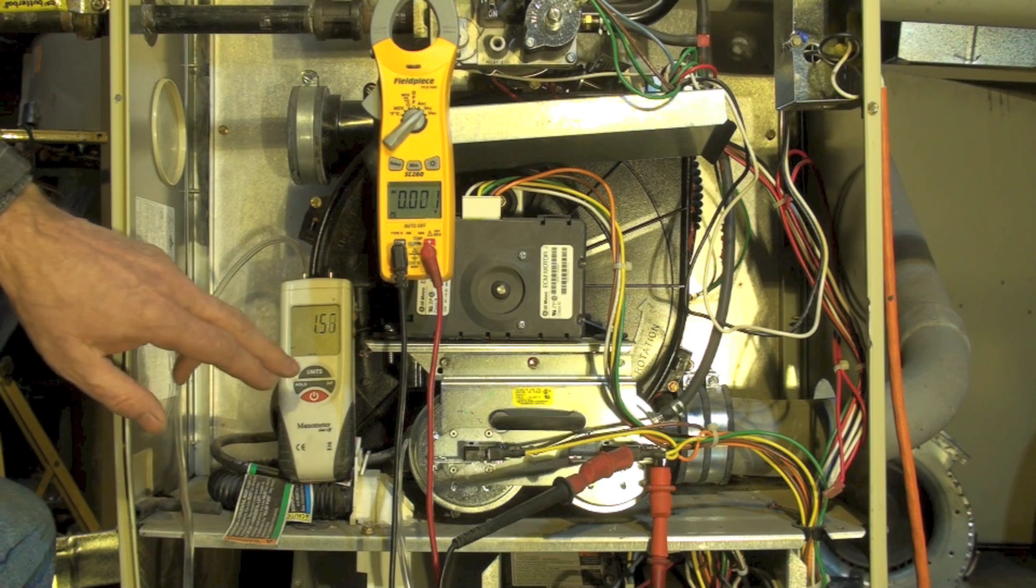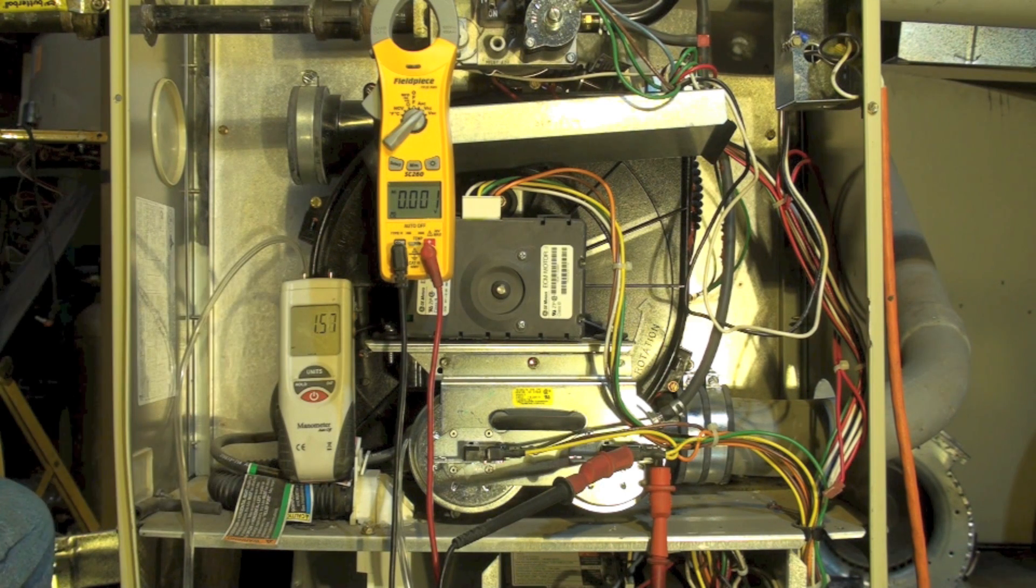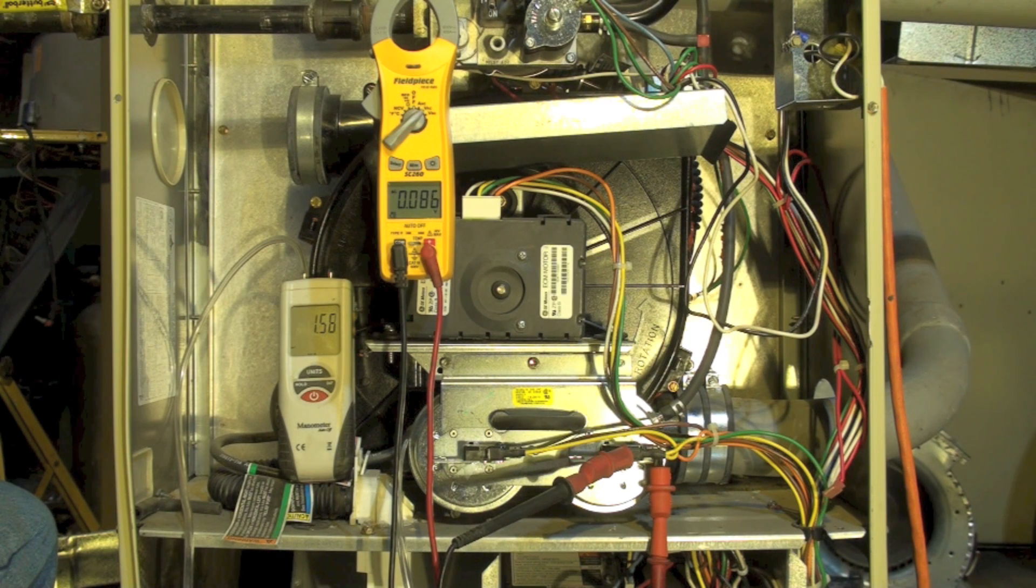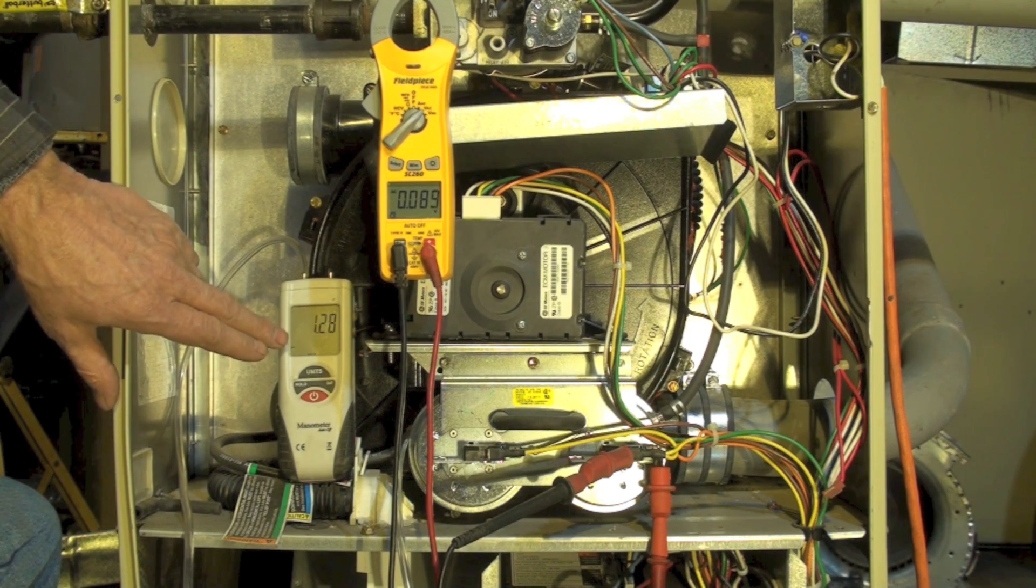Now you notice our vacuum is staying high. I heard the little click for the hot surface igniter. Gas valve is on. Okay, the burners on now.